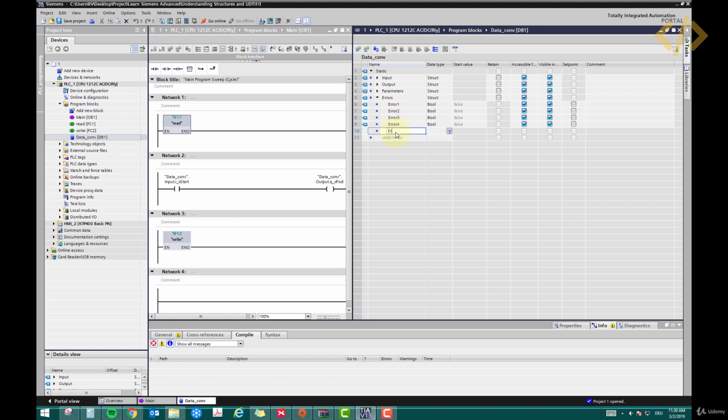And then I will write error com. Now what is error com? In the function we will mention if any of the errors comes, we have an error common boolean bit which will be on, and this bit we will use to indicate that yes, the conveyor has an error. But which error is that? Then we have to read which of the bits is on. Okay, but we just take error common so that we don't have to write 4 errors everywhere. We just use one error common and use it for interlocking and stopping the conveyor. Okay, so we have these 4 structures.